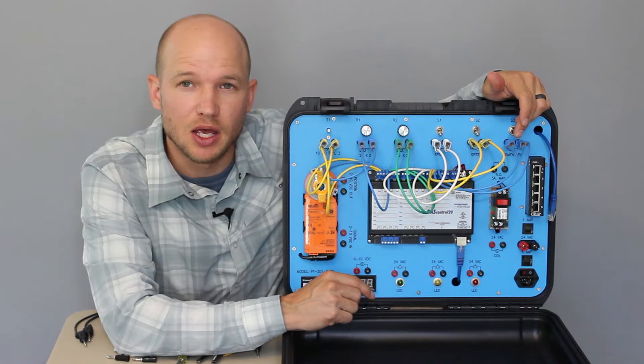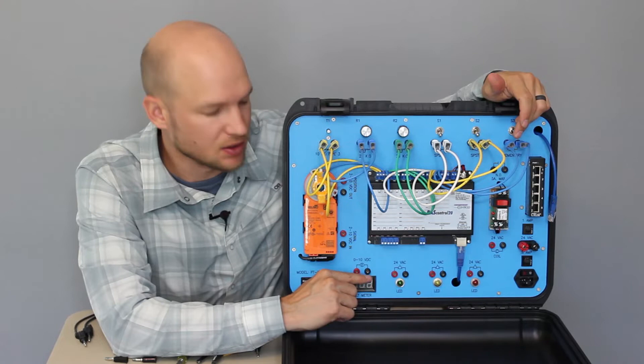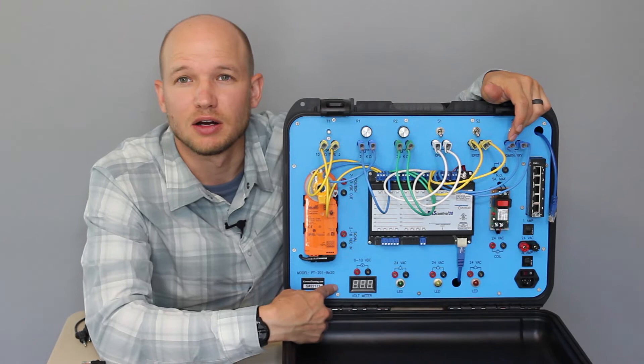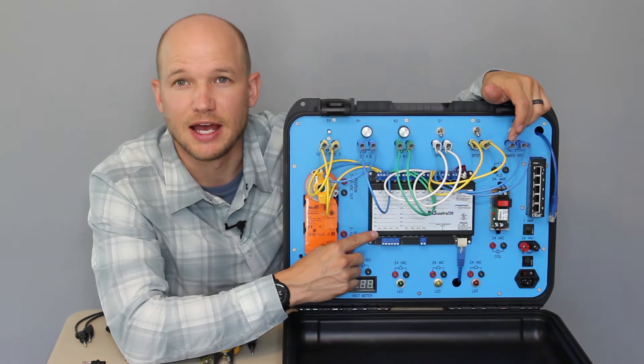So the black is going to be our common, which is on the controller labeled as a C. And if you see on the controller way over here, it says DC common or AC low. And so the red is going to be our AC high or DC plus. And on the controller that's labeled as A for the input and outputs.